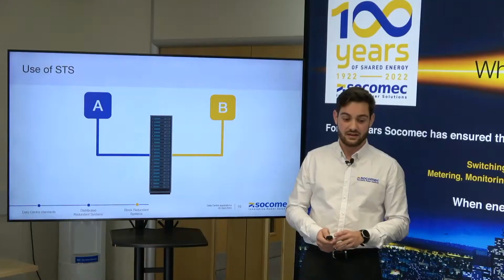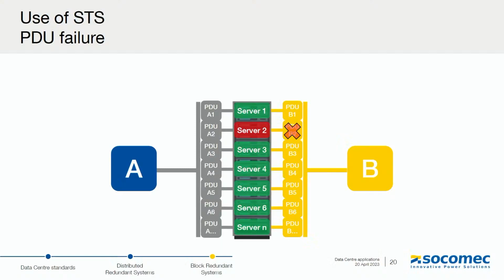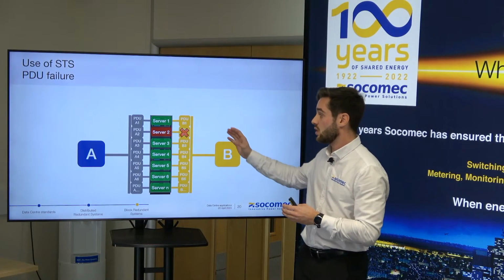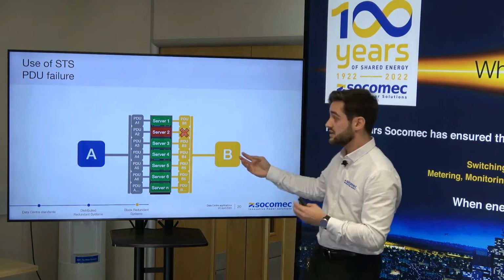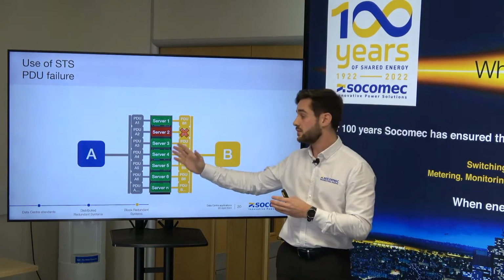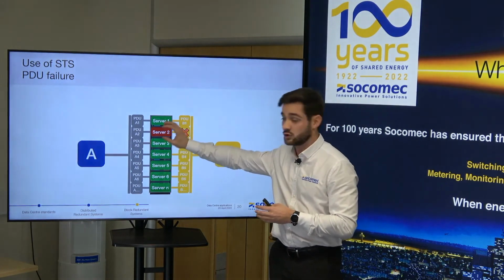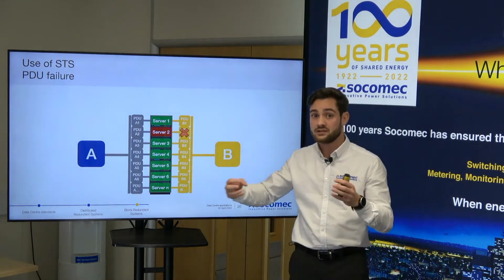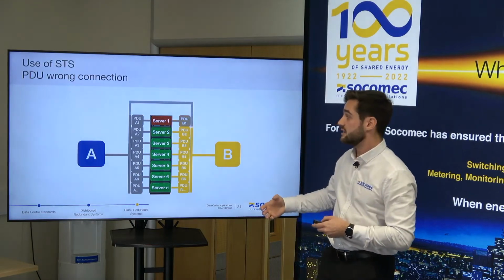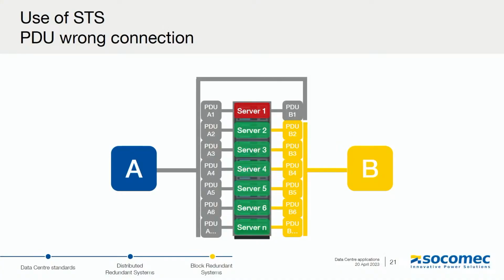Absolutely. So imagine you've got an installation with 2 power paths coming from 2 different UPS systems, A and B. You don't have any STS installed, and you've got a failure on one power distribution unit on one side of the dual corded server. The risk is if you lose the power path coming from UPS A, then you would drop this server because it doesn't have any other power path to rely on. Exactly the same if at day 1 a connection has been made wrongly and both the cords on the server, the dual corded server, have been fed from the same power path.